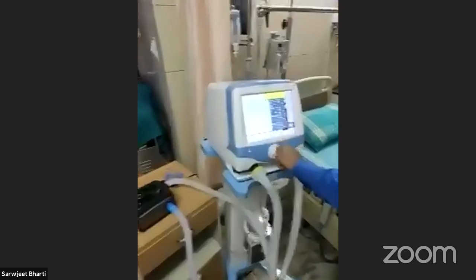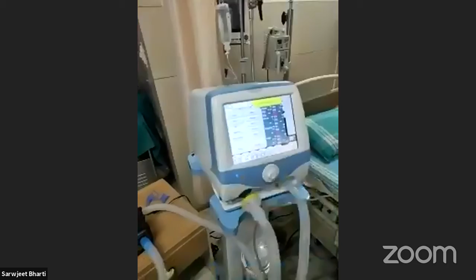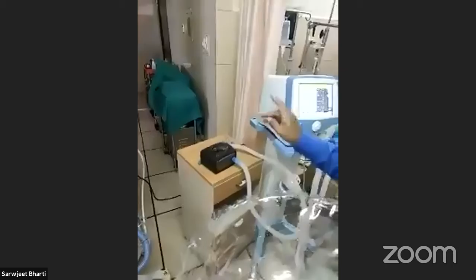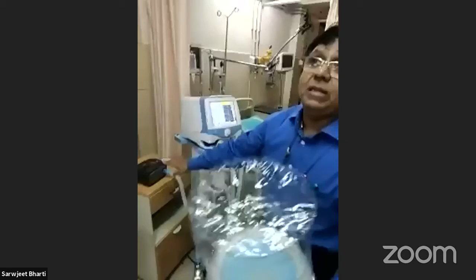Can the same pressure be given when using this helmet instead of a BiPAP mask? Okay. Whenever we use a helmet with the ventilator, I can vary the pressure. I can go to pressure support levels, very high pressure support levels. I can vary the respiratory rate. You can change the inspiratory trigger. When you use this with, let's say, a BiPAP machine, the pressure generated in a BiPAP machine is very low compared to a ventilator. We don't have much control on a BiPAP machine. We have control only on IPAP, EPAP, and we can go maximum up to, I think, 30 centimeters of water with a BiPAP machine. And with high flow also, we have certain control on it. But if you use this with a ventilator, definitely we have excellent control on pressure support.